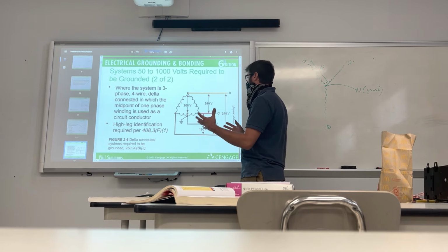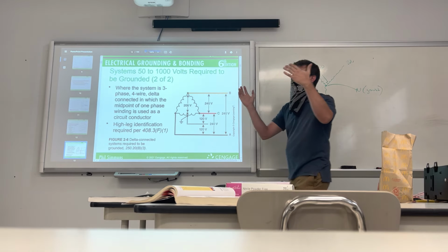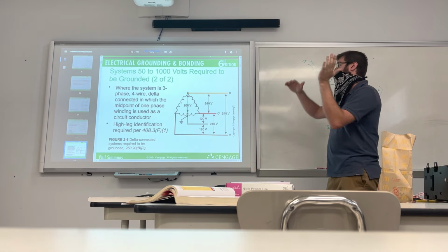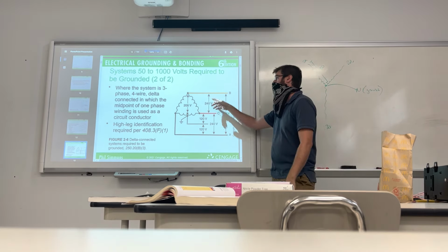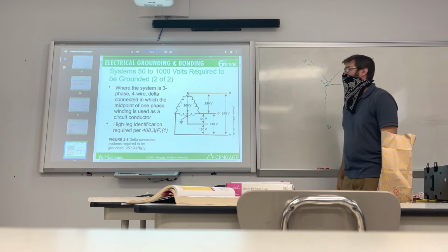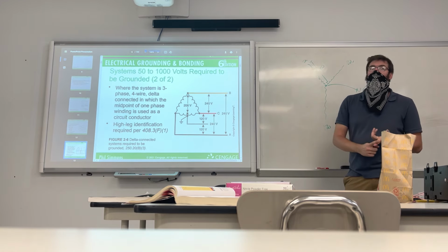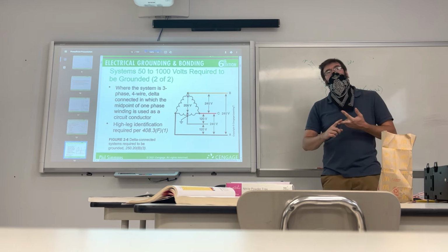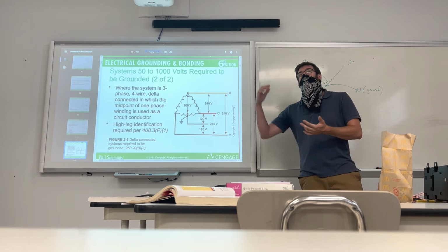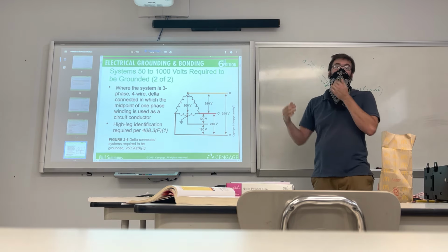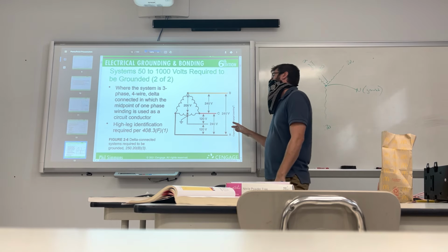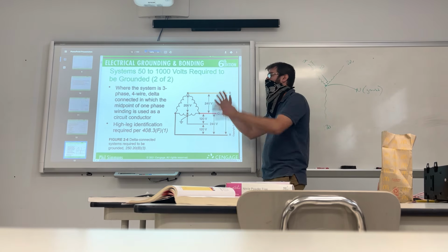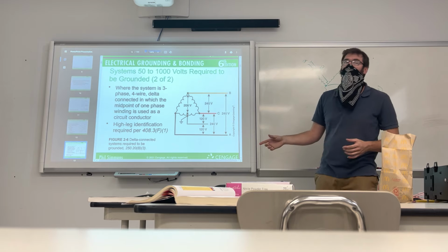So you can have two separate panel boxes. You can have one panel box coming in and it's just two 120s. You can have another panel box with three legs of 240. That's common if you want to run the receptacles and the light circuits off of 120, whereas you have three-phase motors or bigger things operating at higher voltages to keep the amps low. So there are situations where you'll have two separate voltages coming into the building off of the same transformer.